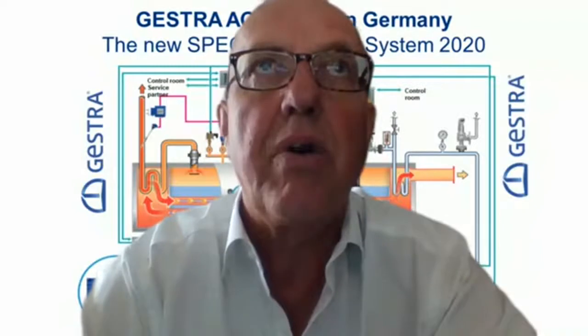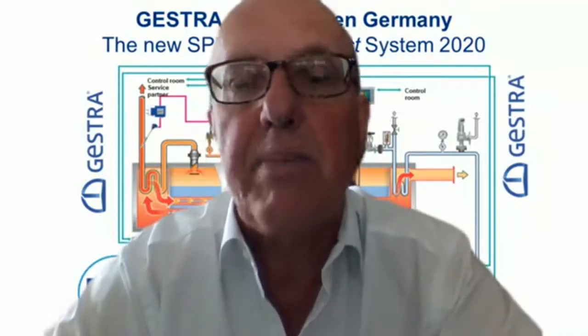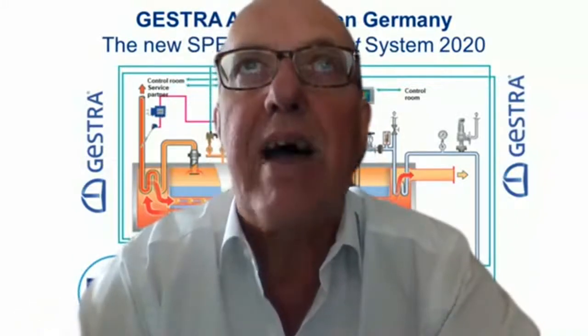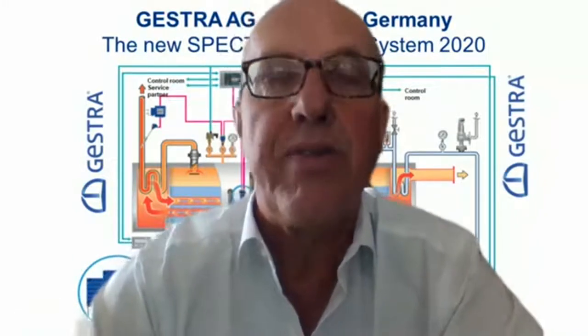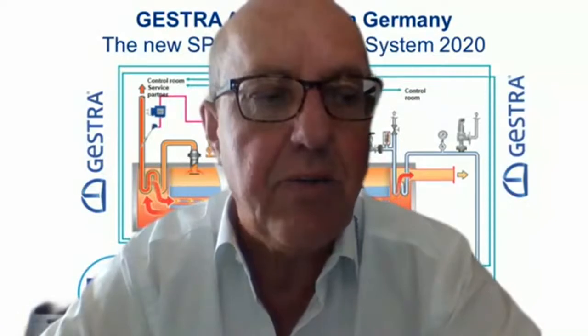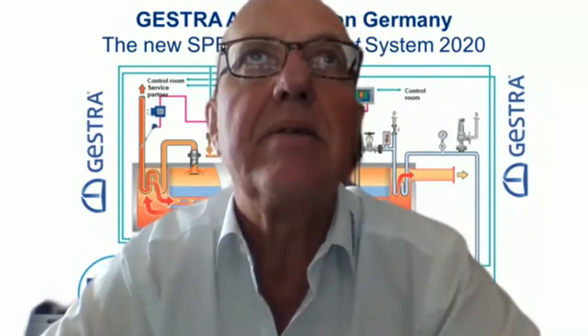This is only possible if you have not more than, I would say, 100 kilograms per hour condensate load, because with a higher condensate load you have all the internal noises in the steam trap caused by flash steam, and so the ultrasonic possibility is not possible anymore. There we have to use the vaposcopes, the sight glasses, if we have a larger amount of condensate. But most steam traps, I would say more than 95%, are working with smaller amounts of condensate. And there we can really find out very well with this device what happens inside the steam trap.